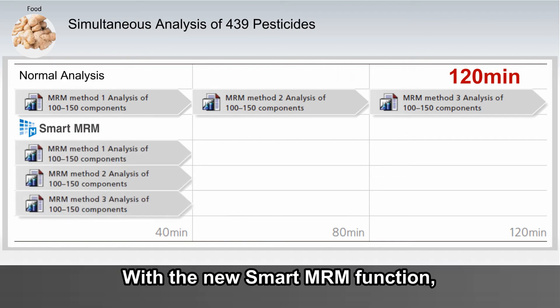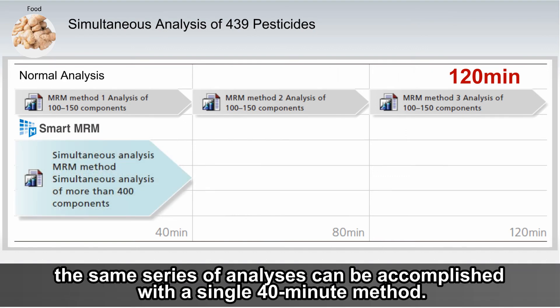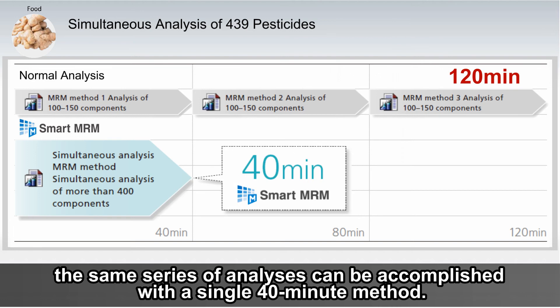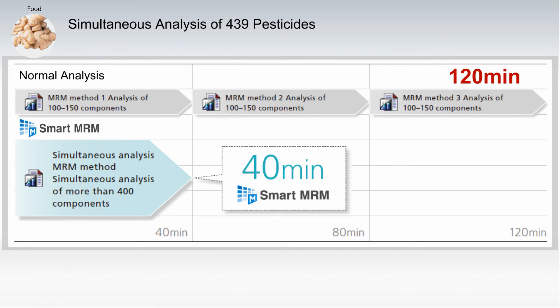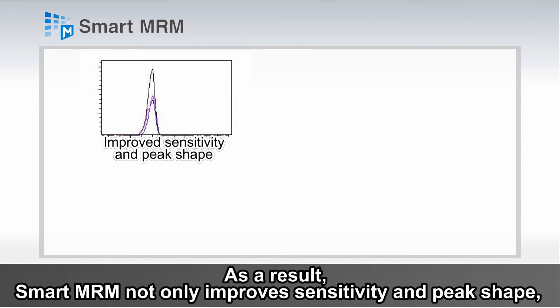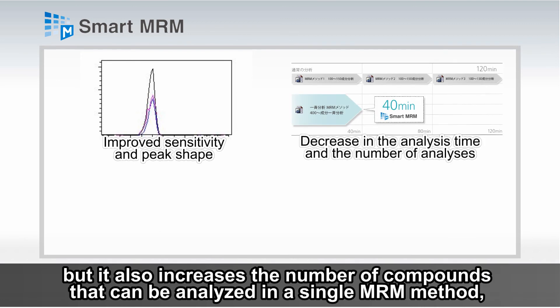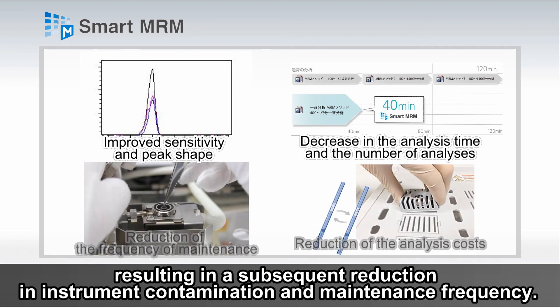With the new SMART MRM function, the same series of analyses can be accomplished with a single 40-minute method. As a result, SMART MRM not only improves sensitivity and peak shape, but it also increases the number of compounds that can be analyzed in a single MRM method, resulting in a subsequent reduction in instrument contamination and maintenance frequency.